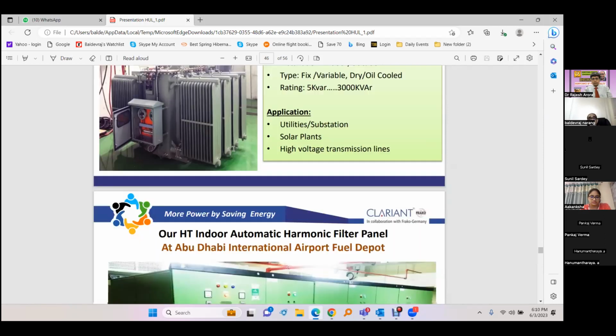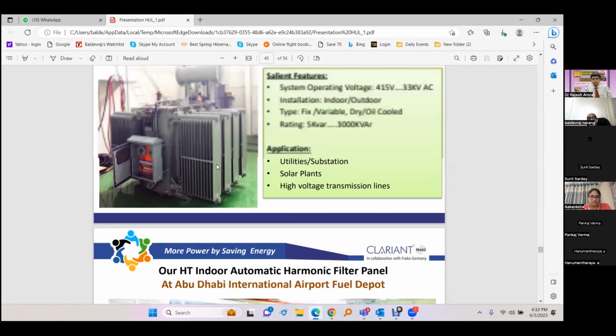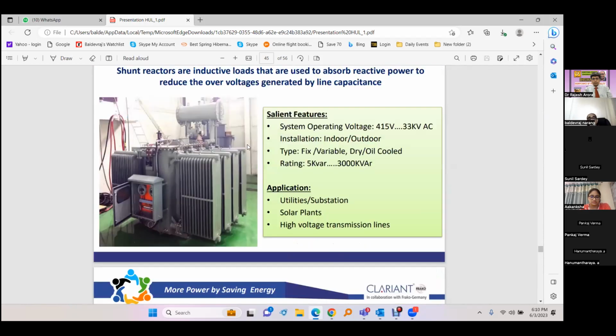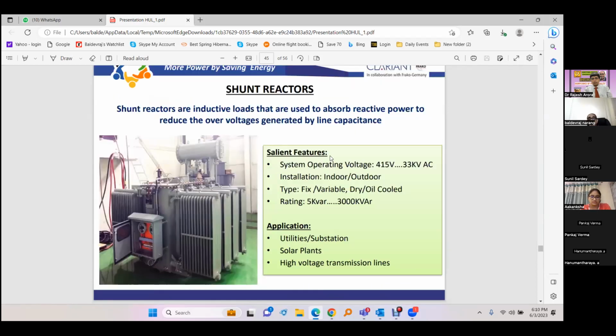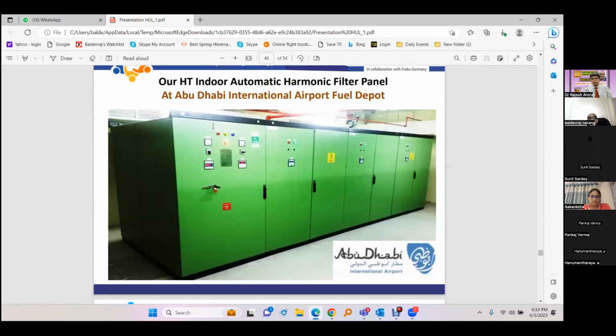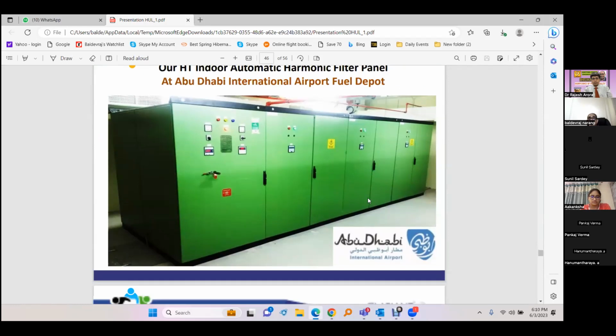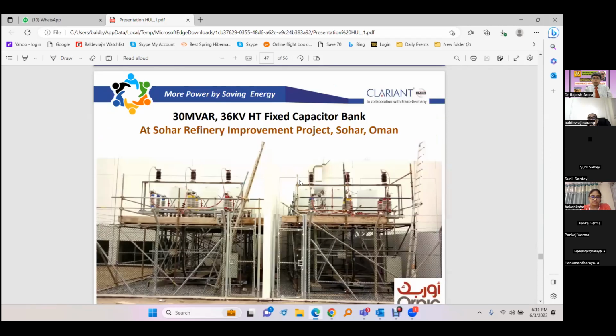And this was done first for one plant, and then they repeated it for another plant also. So this is again an automatic capacitor bank given to Abu Dhabi International Airport. They are HT banks, 3.3 kV banks here. This is a 33 kV system. 30 MVAR given to Sohar Refinery Improvement Project. This is again switched capacitors only, and they are fixed. And now these days we have automation also.